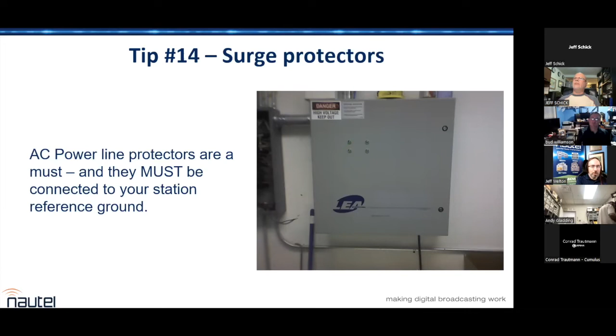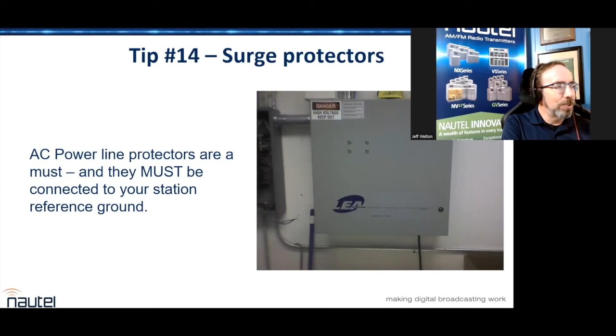It'll sit there with the lights lit, and that's wonderful. But the first storm comes up, the transmitter blows up, support gets a call: 'hey, this transmitter's a lemon, it blows up every time there's a storm,' and the surge protector never flickers. Perfect example of what happens if the surge protector doesn't have a solid ground connection to the AC ground, which needs to be bonded to the facility ground. For what it's worth, Article 250 of the NEC has required that since about 2010, so it's part of code now. But like radio engineers, electrical inspectors are aging out too, so sometimes you need to do some educating.